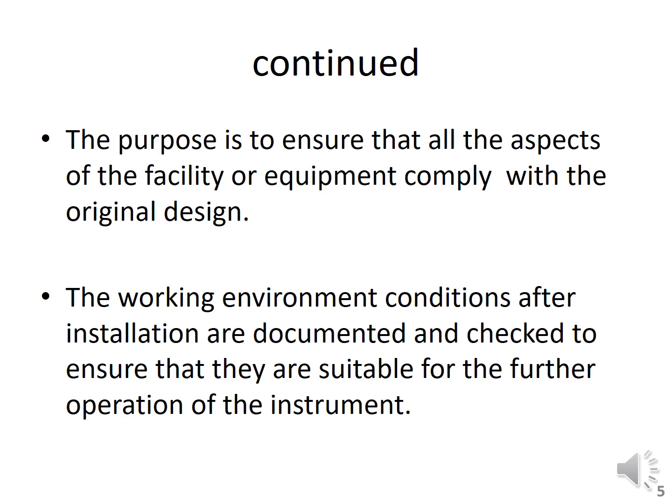with the original design. The working environment conditions are also important, and we say that the working environment conditions after installation are documented and checked to ensure that all these are suitable for the further operation of the instrument.